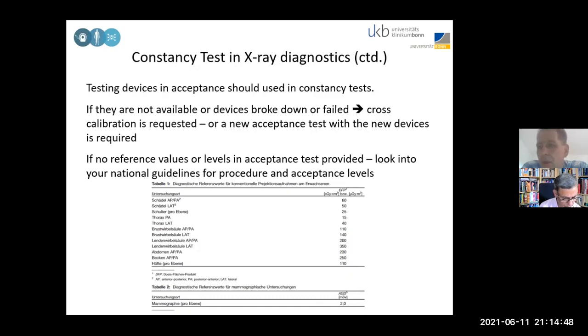As a note for those who would like to introduce a new X-ray device, think about the measurement equipment you should also order together with the machine. Don't rely on the vendor's equipment. I usually only rely on my own equipment because I know what my electrometers, dosimeters, or chambers are doing.